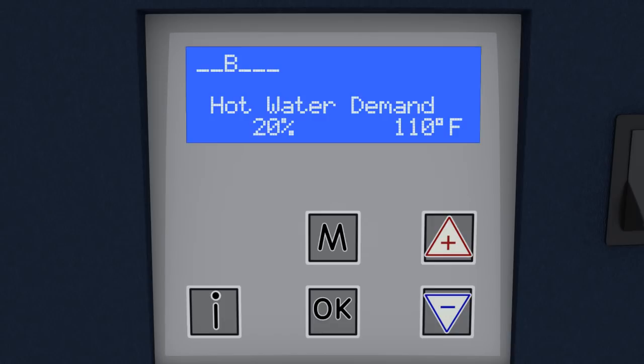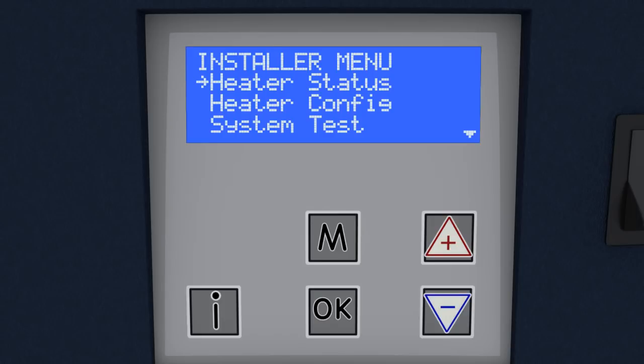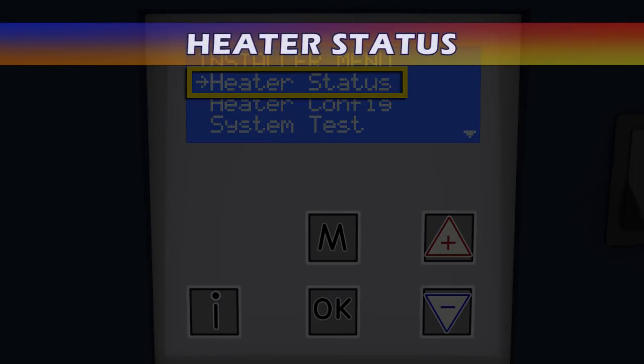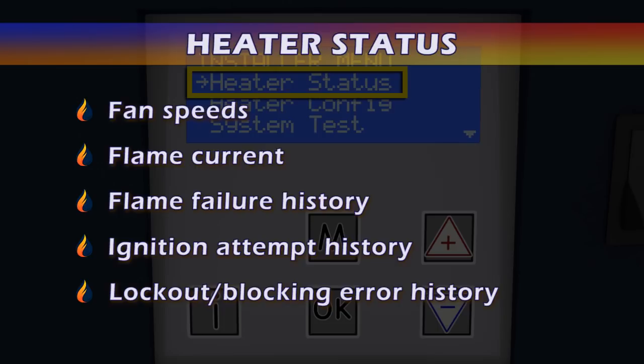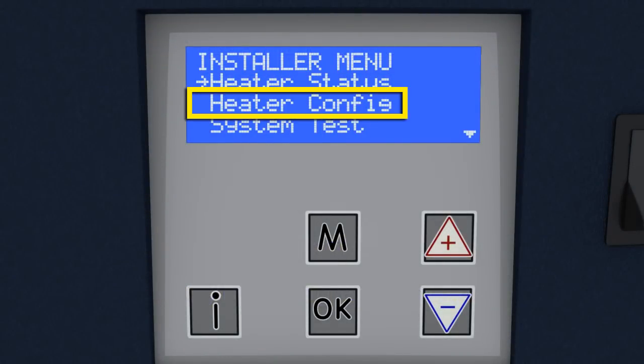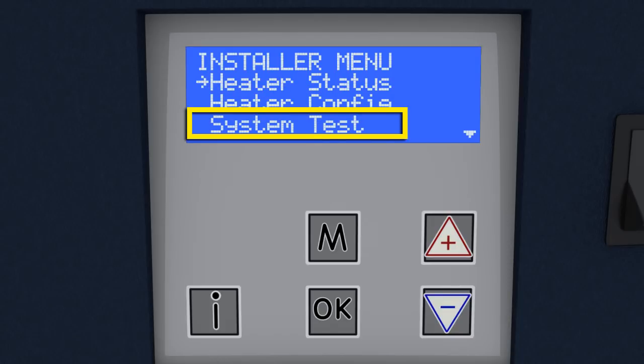System and troubleshooting information such as fan speeds, flame signal, ignition attempts, and error history is available in the Installer menu on the control display. To access the Installer menu, be sure the display is on the home screen and hold down the OK and M buttons together for 5 seconds. The Installer menu screen will be displayed, followed by the heater status, heater config, and system test submenus. The heater status submenu contains useful real-time information pertaining to fan speeds, flame current, flame failure history, ignition attempt history, and lockout blocking error history. This menu can be used when troubleshooting the water heater. The heater config submenu can be used to set a service reminder. See the manual for more information on using the system test submenu.